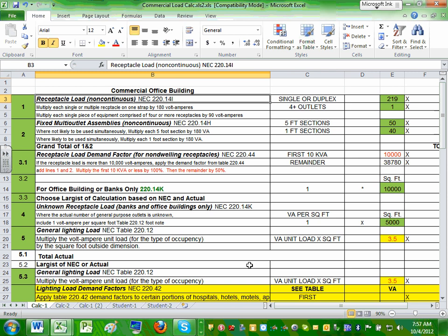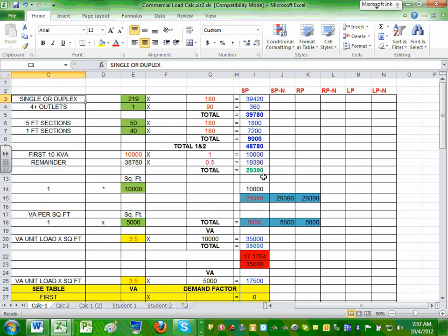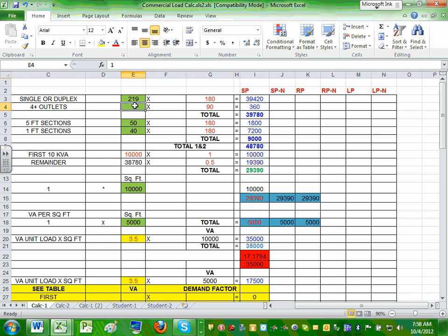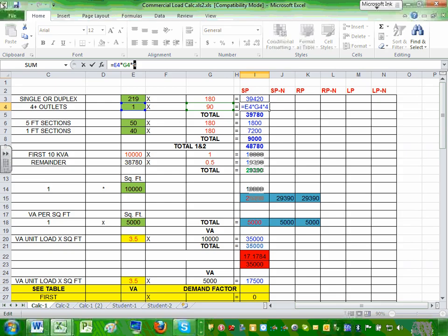Article 220.14(i) tells you for a single receptacle, you multiply by 180. This will be the number of your single receptacle yoke or duplex receptacle yoke, multiplied by 180. If you have a quad — four receptacles in one yoke — you count them as one and multiply by 90, then multiply by 4. So if you have a quad, you take the number of quads, multiply by 90, and multiply by 4.